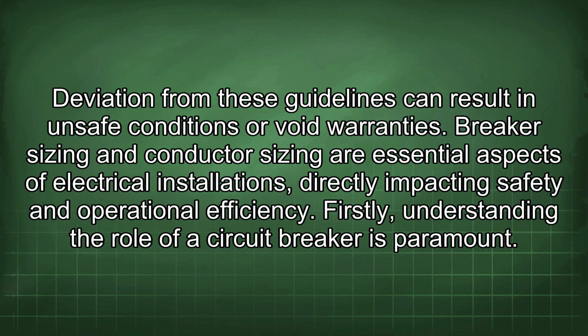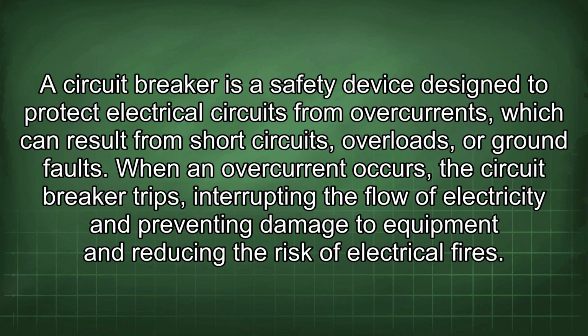Breaker sizing and conductor sizing are essential aspects of electrical installations, directly impacting safety and operational efficiency. Firstly, understanding the role of a circuit breaker is paramount. A circuit breaker is a safety device designed to protect electrical circuits from overcurrents, which can result from short circuits, overloads, or ground faults. When an overcurrent occurs, the circuit breaker trips, interrupting the flow of electricity and preventing damage to equipment and reducing the risk of electrical fires.